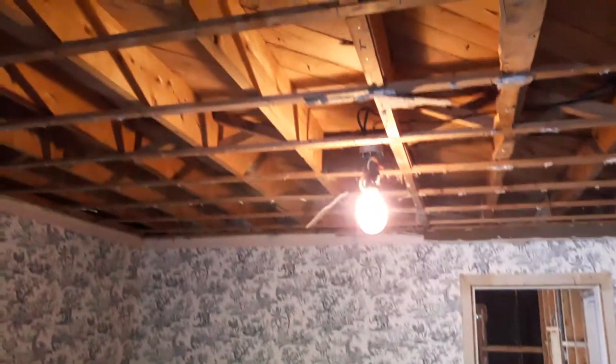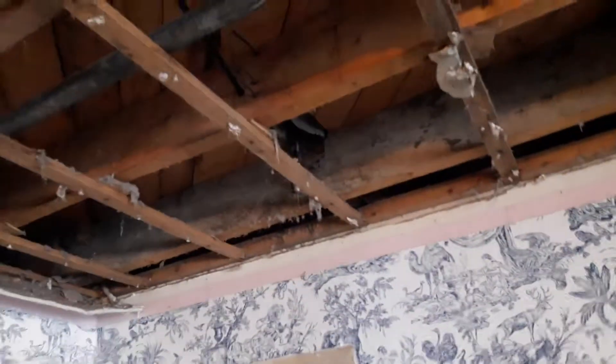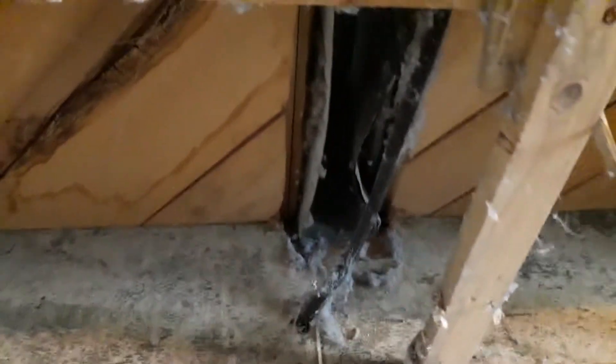Day three on our white kitchen project. We had just taken down the ceiling, which was the original drywall in the future kitchen. Here's a message to all of you: never ever use a joist cavity for your ductwork. You can see here's the outlet through the floor, and look at all the mess that has accumulated.